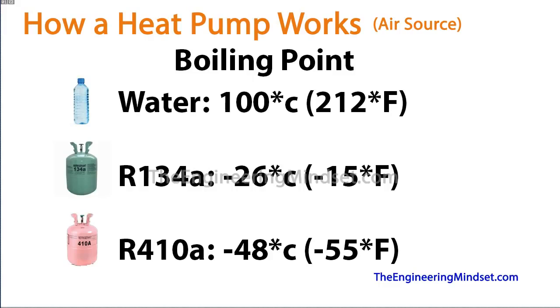So as long as the air temperature outside is above these boiling points, then you can extract the energy from this air and move it across and into the inside of your building. But heat pumps generally work off of electricity. The compressor is powered by electricity, so the higher the temperature of the air, the greater the efficiency. So once you get down to maybe just above this boiling point here, it's not going to be very cost effective or efficient to actually run this system. However, you can still extract energy. So it will work, it will just cost you quite a lot of money to run it at this temperature.